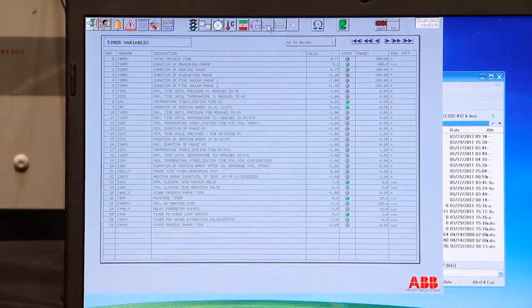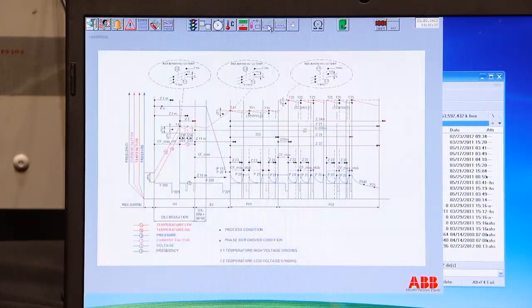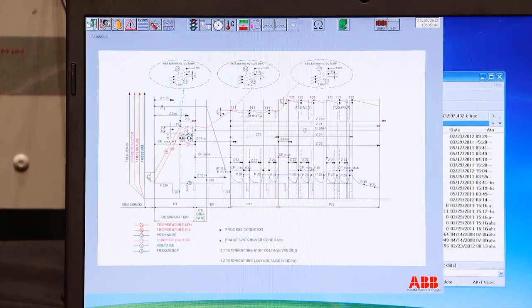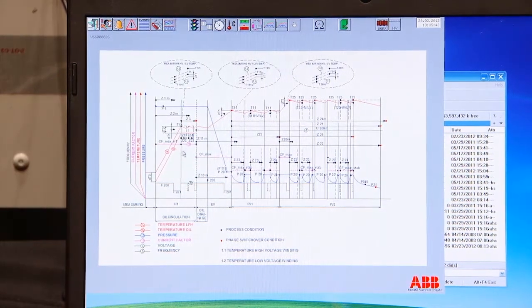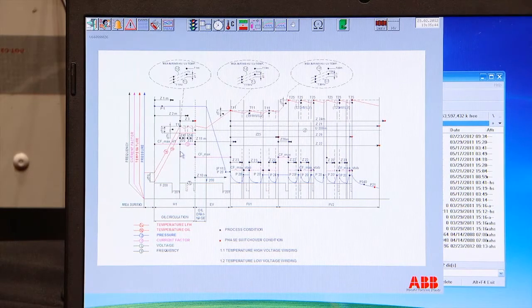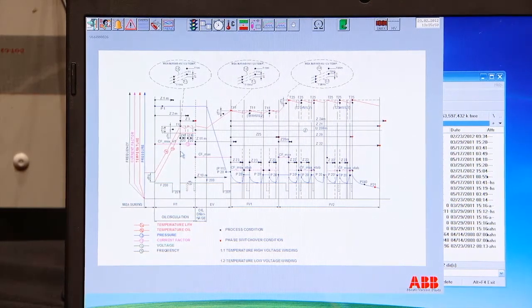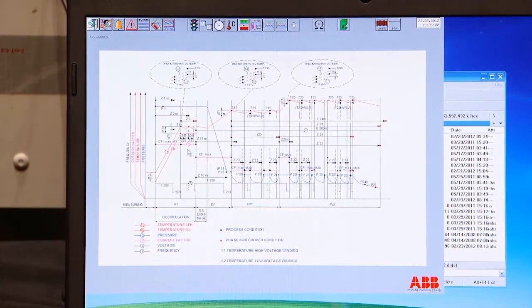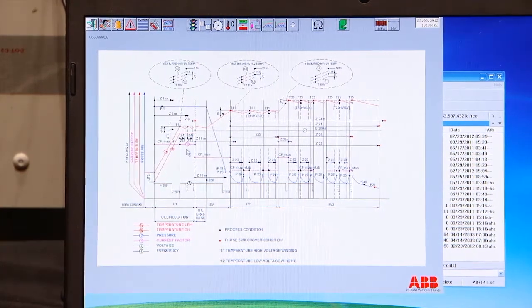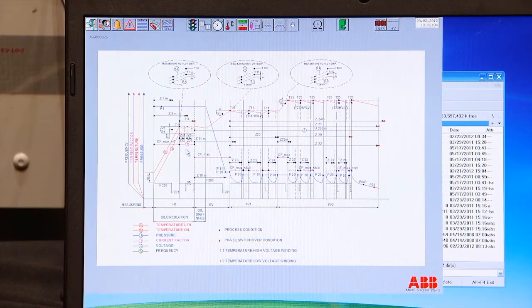Stabilization, yes. On this page here, you have the process. 4-hour time period there then? The 4 hour time period is how long we keep this stabilization. Heating, okay, waiting half an hour, heating, waiting half an hour, for 4 hours. Okay. And that's now just in factory testing that we do these short heating breaks. Normally when you're heating up from 80 to 90 degrees, then you go for 6 hours or 8 hours heating breaks.